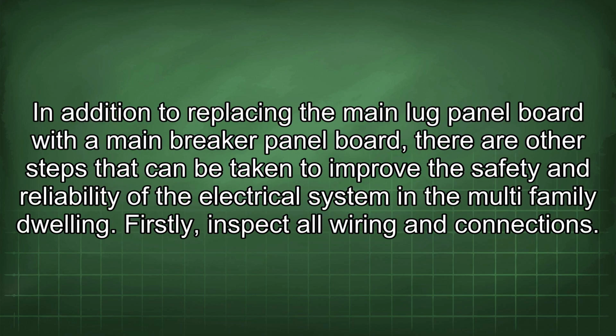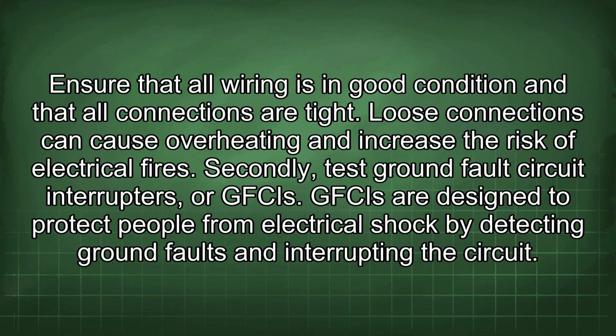In addition to replacing the main lug panel board with a main breaker panel board, there are other steps that can be taken to improve the safety and reliability of the electrical system in the multifamily dwelling. Firstly, inspect all wiring and connections. Ensure that all wiring is in good condition and that all connections are tight. Loose connections can cause overheating and increase the risk of electrical fires.